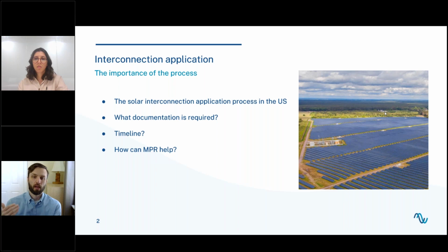Those are things like a PSSE model or a three-phase EMT model, usually done in PSCAD or EMTP-RV, among other software. But then there's a whole host of other documentation that's required, and this is really where pvDesign and Rated Power come into play. Documentation such as the single line diagram, the tie line impedance, transformer data such as the main transformer and the inverter step-up transformers, and then the collector system equivalent impedance.